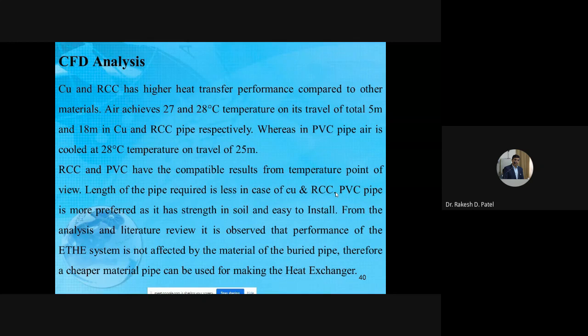The length of pipe required is less in the case of copper and RCC. PVC pipe is more preferred as it has strength in soil and ease of installation. There are some installation problems and some strength issues in copper and RCC pipe. So I am preferring the PVC pipe for the heat exchanger. From the analysis and the literature review, it is observed that the performance of the heat exchanger is not affected by the material for the buried pipe. Therefore, a cheaper material pipe can be used for making the heat exchanger.